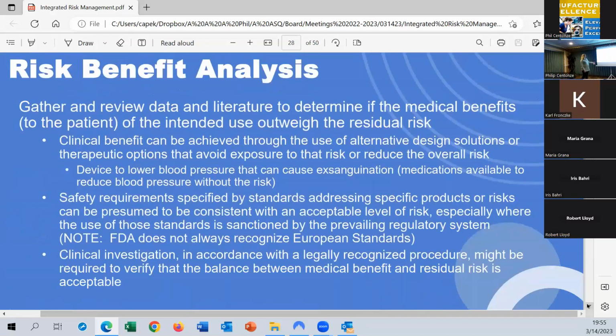Right, so risk-benefit analysis is, like I said, a way of looking at different things: the clinical benefit that's achieved through the use of the product, the safety requirements, and if there's other ways for the user to achieve that benefit without the same level of risk, with a lower level of risk. If our risk-benefit analysis says that the benefit of using our product is worth it, right, is better than the risk, then we can continue to use our product, even if we have high levels of risk, right? For some of these, like a ventilator, it might pose some risk, but if the alternative is, well, you can't survive, it keeps you alive at least, then that's going to be worth the risk if there's nothing else that would do the same function.